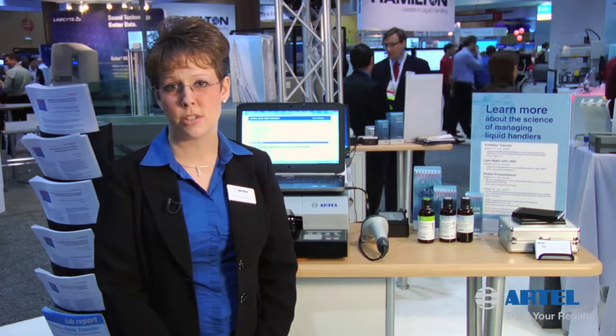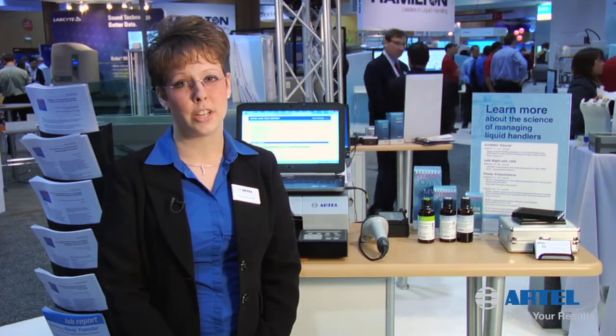Measurement down to 10 nanoliters allows our customers who are using acoustic droplet dispensers to quickly and efficiently calibrate the performance of their liquid handlers, which allows standardization across multiple labs, locations, and around the world. For more information on the Artel MVS and the 100% DMSO sample solution, please visit Artel-USA.com. Thank you.